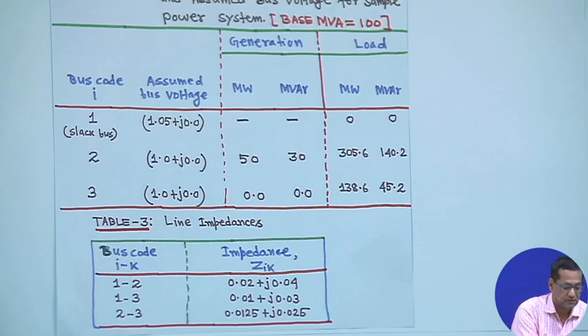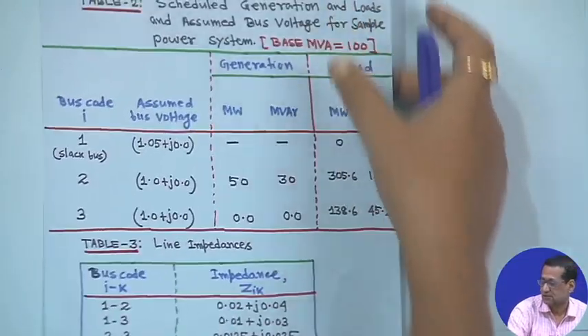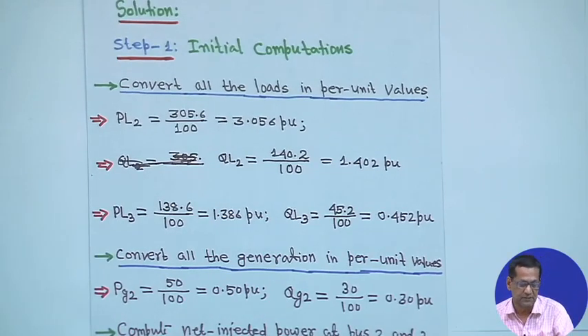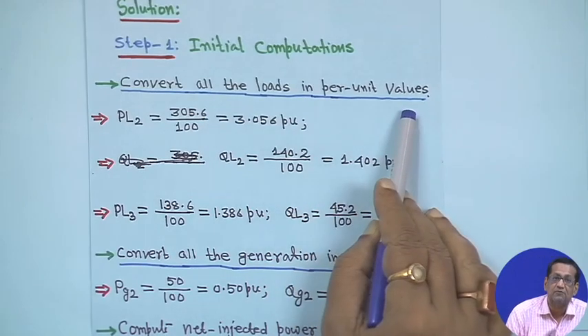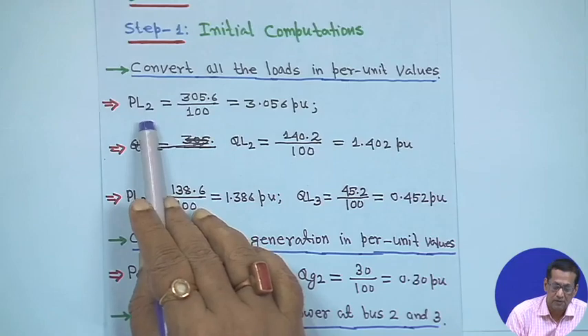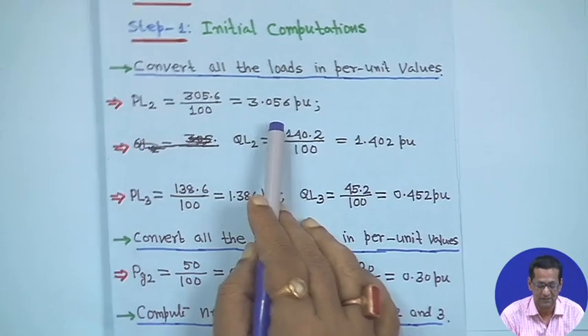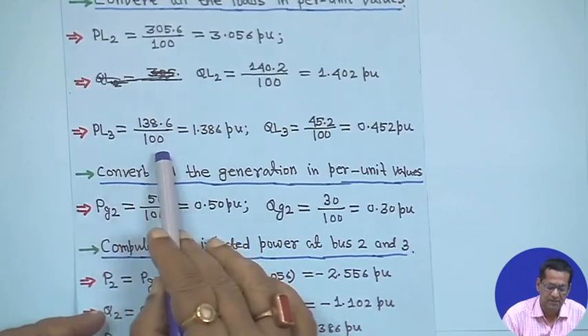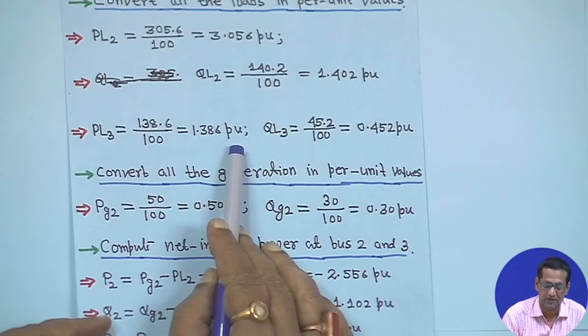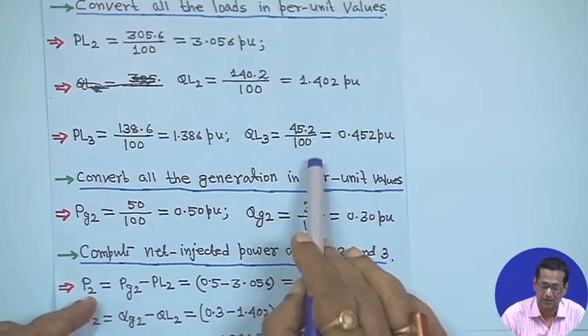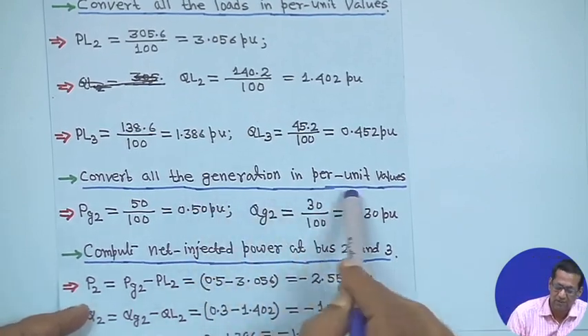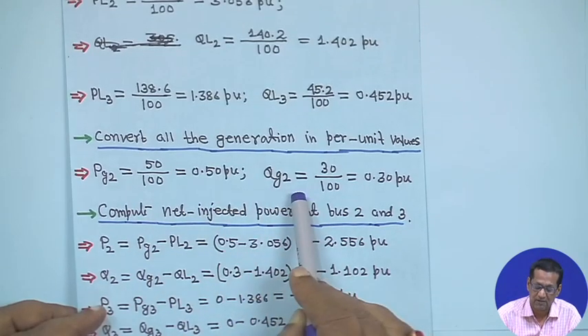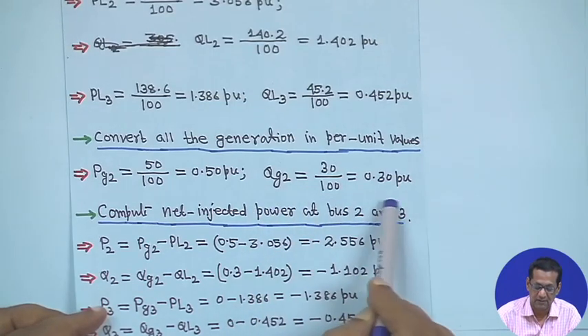Step 1: Initial computations — convert all loads and generation to per unit. At bus 2: PL2 = 305.6/100 = 3.056 pu, QL2 = 140.2/100 = 1.402 pu. At bus 3: PL3 = 138.6/100 = 1.386 pu, QL3 = 45.2/100 = 0.452 pu. For generation at bus 2: PG2 = 50/100 = 0.5 pu, QG2 = 30/100 = 0.3 pu.